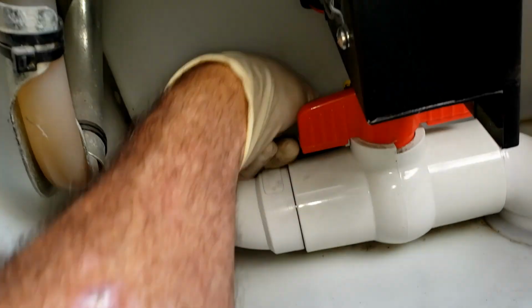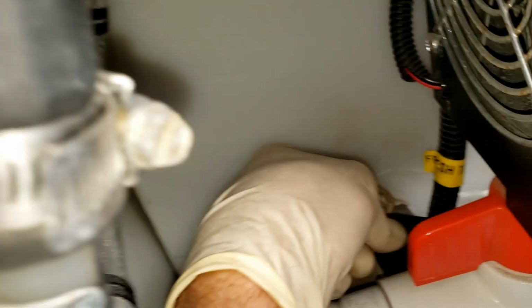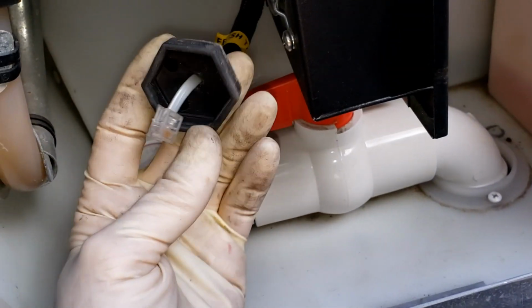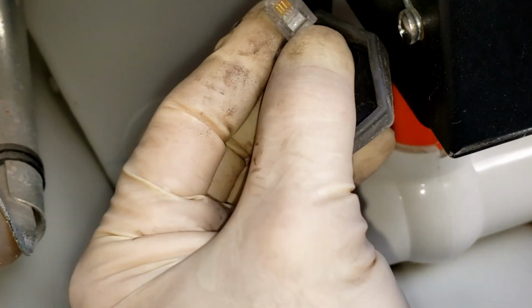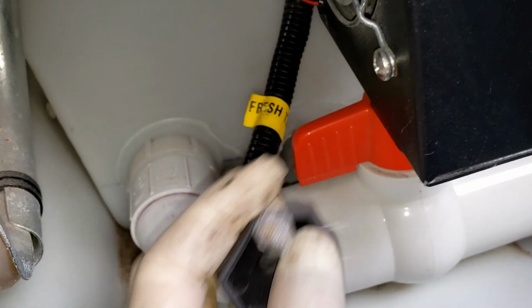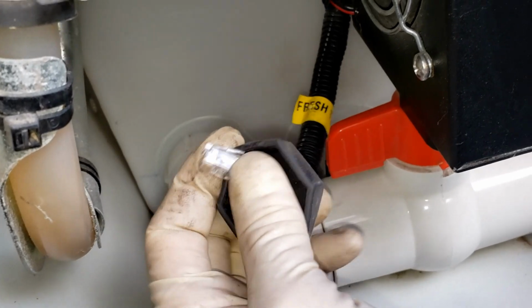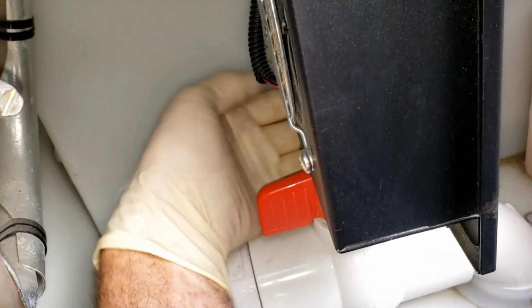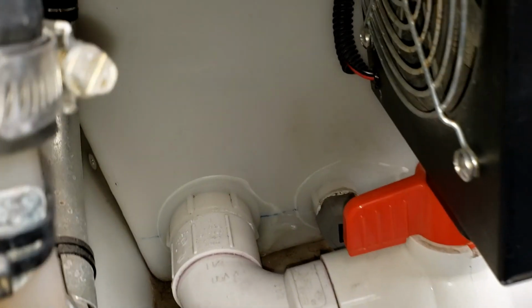The valve is open and just barely leaking anything out because we're empty. So what we've got to do first is pull back this rubber cap to get it out of the way so you can unplug the connector. So there it is, pretty straightforward. Always inspect this and make sure it doesn't have corrosion on it, because it is a water sensor and it could have leaked - there's no reason to replace it if the connection's not going to work well.